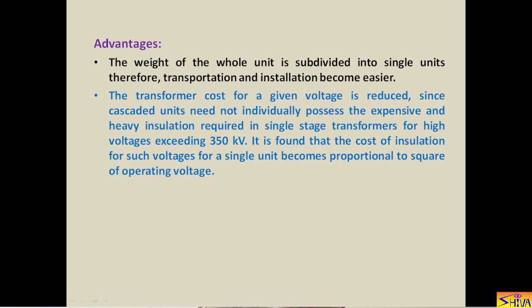As seen in the diagram, the voltage output of each unit is V2 only. So if we have 350 kV rating for the high voltage winding of each unit, the insulation requirement is 350 kV only — not 700 kV for the second unit or more for the third. The cost of insulation for a single unit is proportional to the square of the operating voltage. For example, to generate 600 kV with a single unit, the cost is proportional to 600². Using three units of 200 kV each, the cost is proportional to 3 × 200², which is far less than 600². That is the advantage.